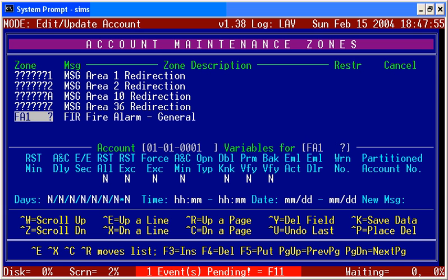Now, also, a lot of times you may see this come in simply as an FA1. That's the reason I like to put in the question marks after that, just to take care of the unknowns. But please note that an FA10 is going to be identified, in this case an FA10 through 19 would be identified in the same zone. So there are some twists and turns here, and I know that when you're dealing with signals coming in, we don't always have a chance to test them all out. But you really have to query your installers about how they're doing that.